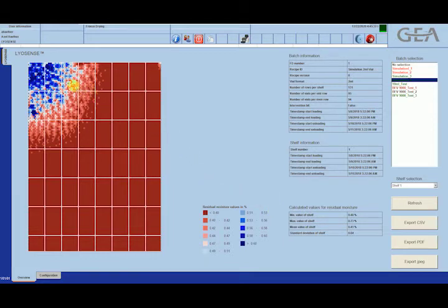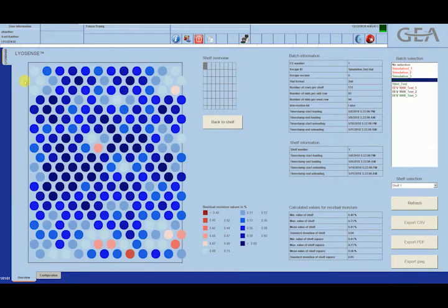You might have recognized that the distribution is divided into different sections. So these sections are also selectable. For example, now our humid spot at the top corner, we could select that one, which would lead us to the next screen, where we have all the single vials which were located on that spot during our freeze-drying process. The vials are also represented in the color corresponding to the moisture content. You see now a vial which is drier than the vials around it, and also this single vial is selectable inside of the HMI application.